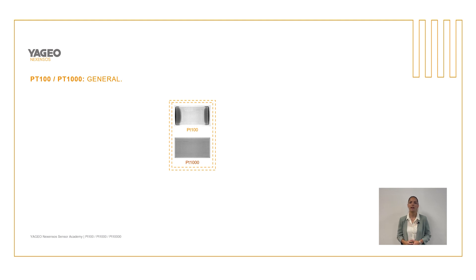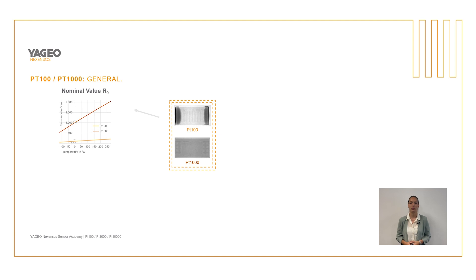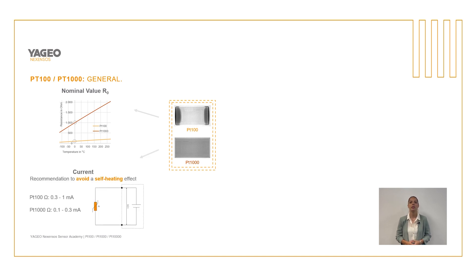On this slide we see a general comparison of the resistance values. The resistance at zero degrees Celsius for the PT1000 is 10 times higher compared to the PT100. To prevent a self-heating effect, the PT100 can be supplied with a higher current than the PT1000. We recommend a measuring current of 0.3 to 1 milliampere for the PT100 and 0.1 to 0.3 milliampere for the PT1000.